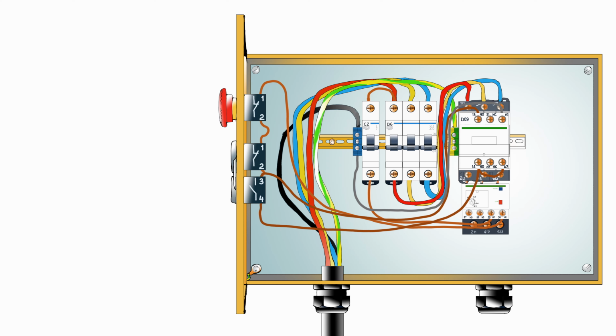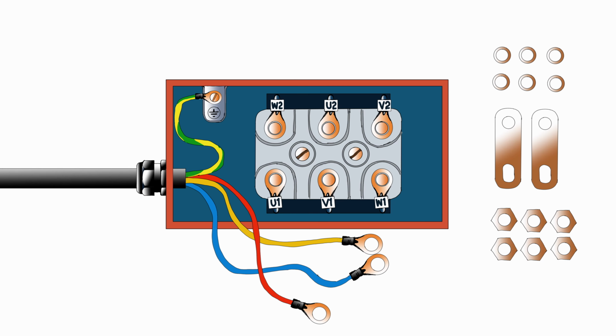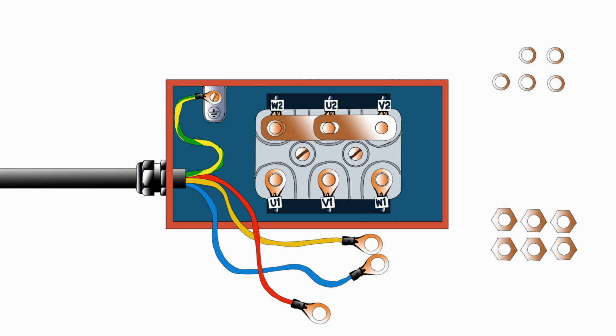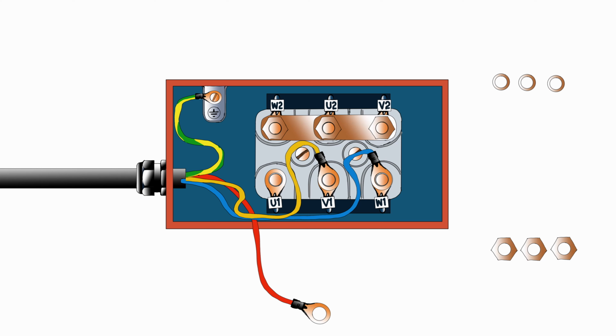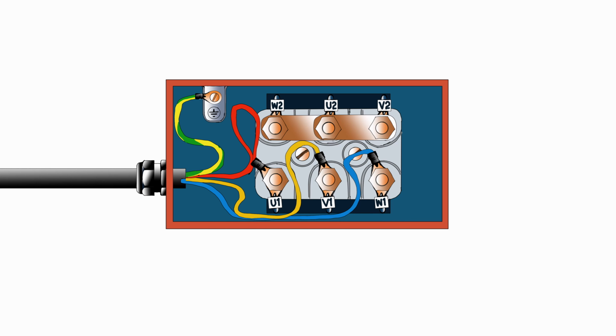At the bottom of our contactor is linked with our overload relay, and then we don't need to link it with any cables there. And then from the bottom of our overload relay, then we connect our supply cable that goes straight to our electric motor. For our electric motor on this exercise, remember, we connect it according to the manufacturer specifications, depending on the supply voltage that you have.